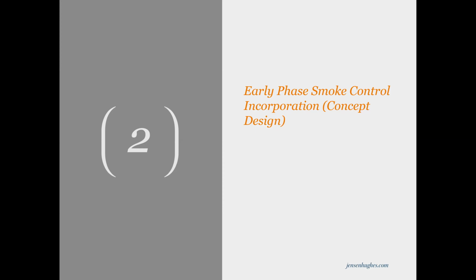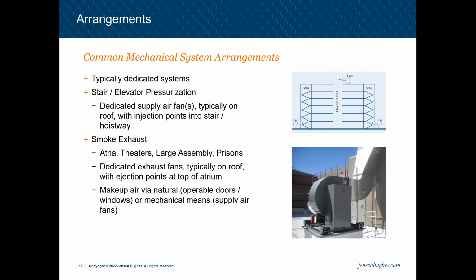So moving along on that timeline, we're going to start looking at the early phase of smoke control incorporation during our concept design. A couple of items that are important to note are the common mechanical system arrangements. They're typically dedicated systems. Our stair and elevator pressurization systems are required to be dedicated. What dedicated means is we have one pressurization fan and its only job is to pressurize the stair during a fire alarm event. The fans are normally located on the roof, but they can be located anywhere throughout the building, on the first floor or the 5th floor. They do require a 2-hour enclosure, including all ductwork that's involved with the stair pressurization.